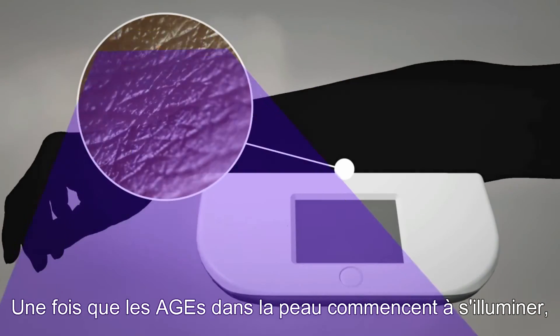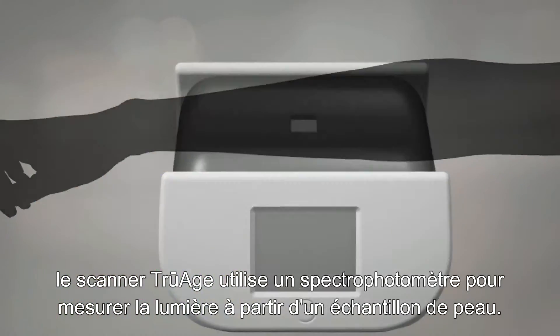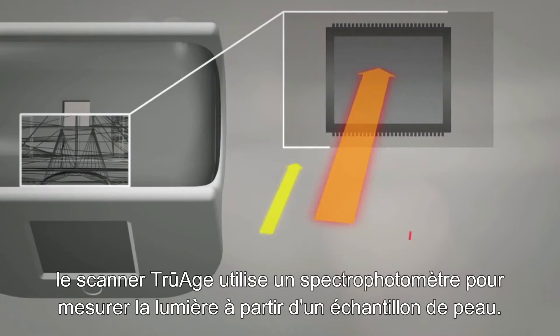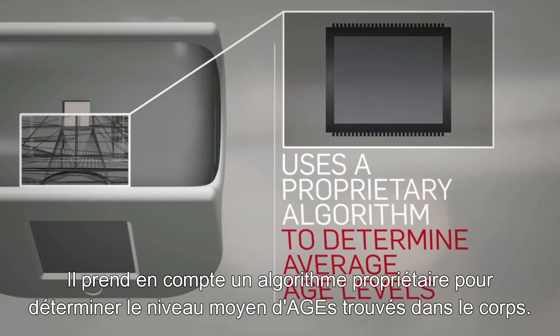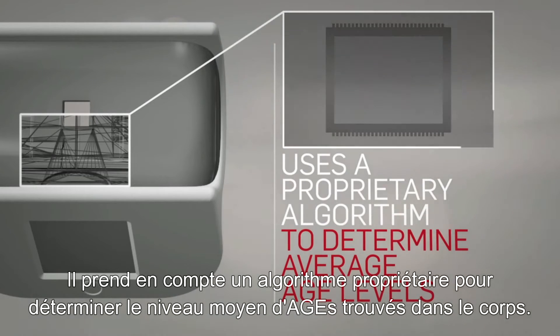Once the AGEs in the skin begin emitting light, the TrūAge scanner uses a photospectrometer to measure the light from a sample of skin. It uses a proprietary algorithm to determine the average AGE levels found throughout the body.